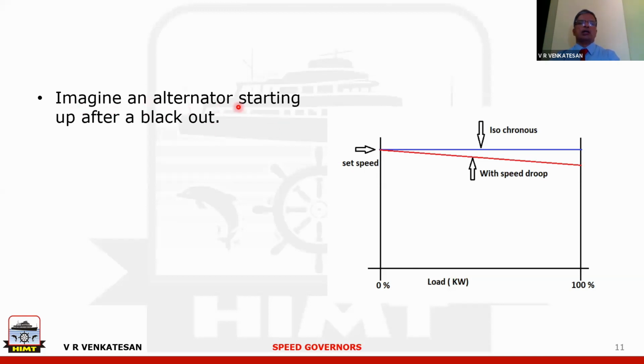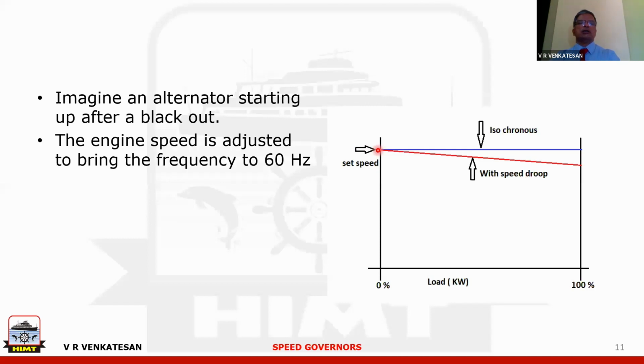Imagine there is an alternator which is starting up after a blackout. There is a complete blackout on board your vessel. So a single alternator has been started. You have adjusted the frequency to 60 hertz. So it has come down to 60 hertz. And at 60 hertz, the circuit breaker is closed. So the kilowatt is still 0. It is running at 60 hertz frequency.